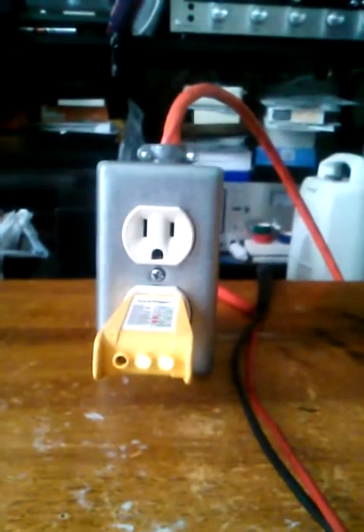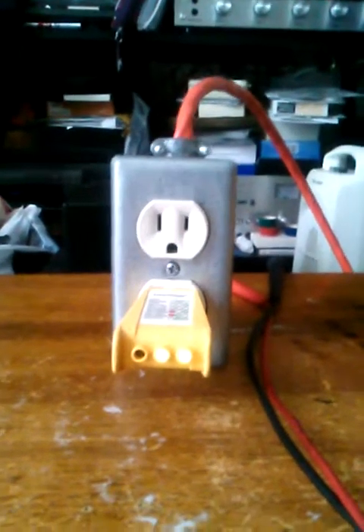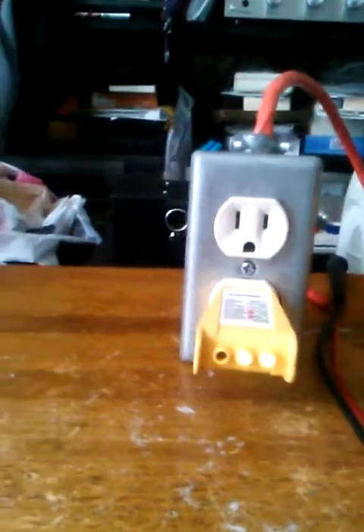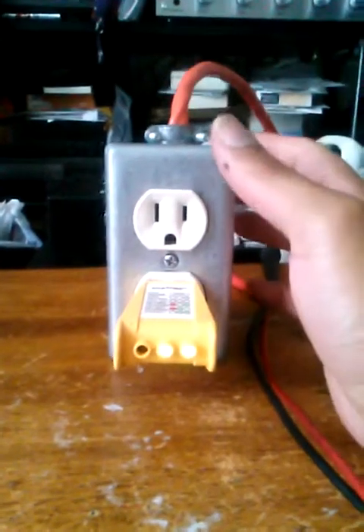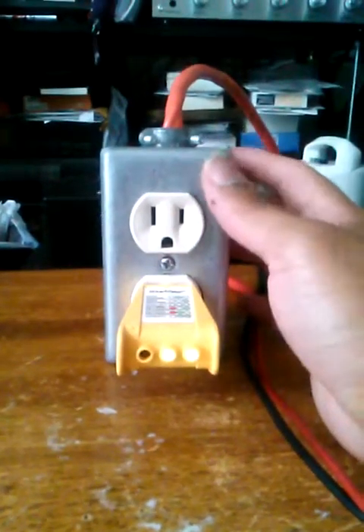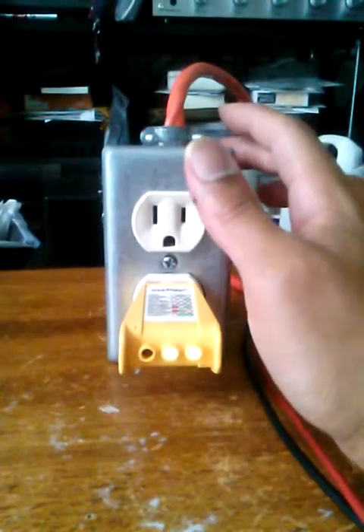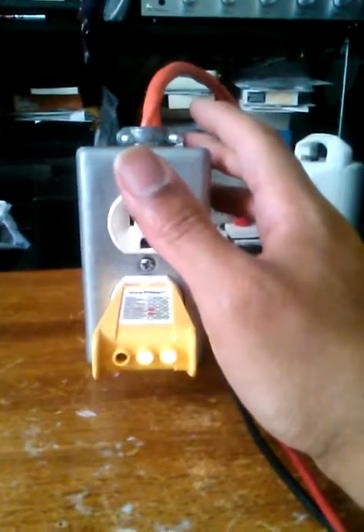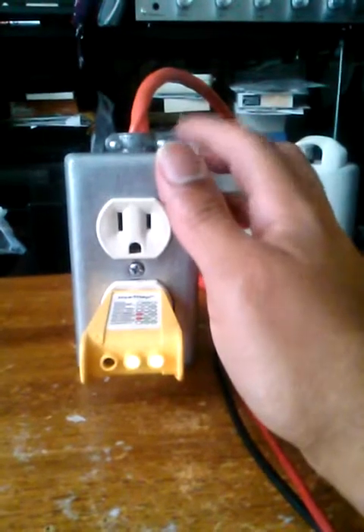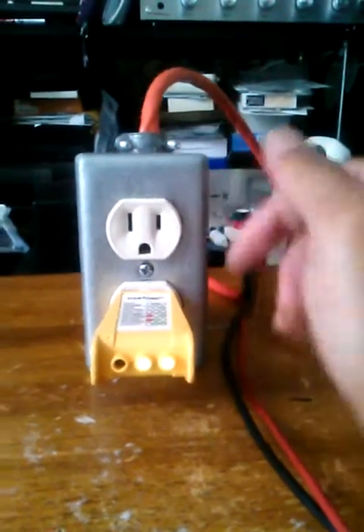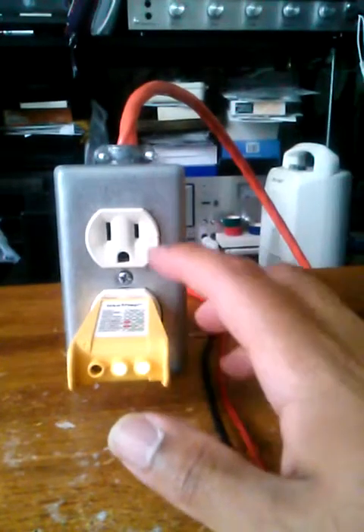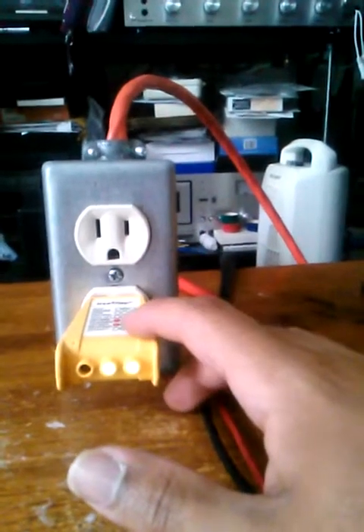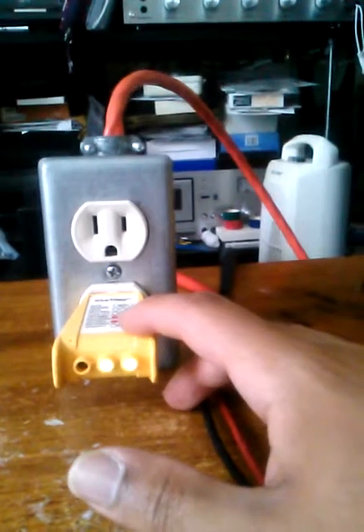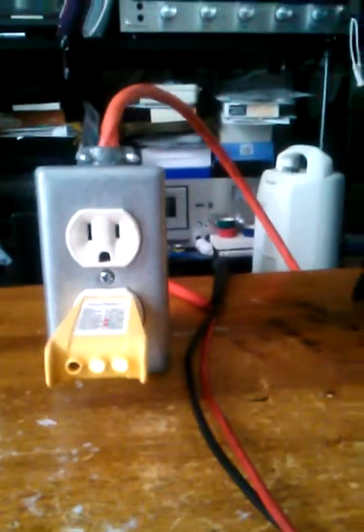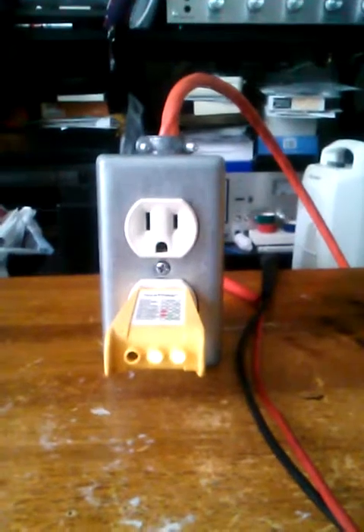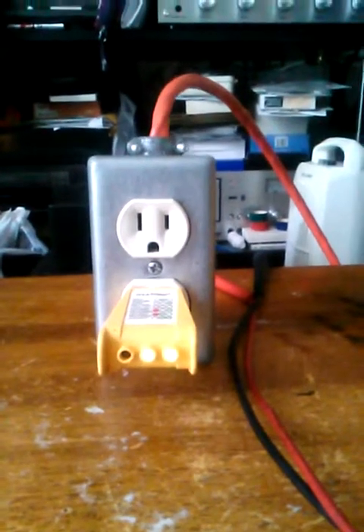If you have the old AC wiring, like I said, the old AC armor clad or BX cabling in your household, that should be nicely tightened and bonded with the box at the outlet, and also at the junction, and also at the service panel. If neither of them is properly tightened, then you're going to have situations where you have an open ground circuit, which is not good for computers and sensitive electronics, such as home theater equipment, surge protectors and UPS backups for your computer or home theater system.